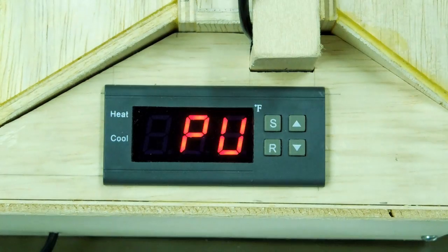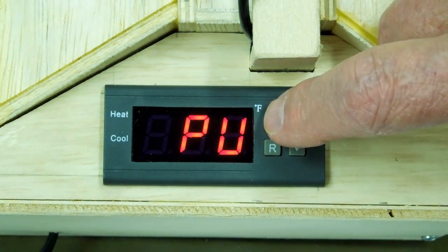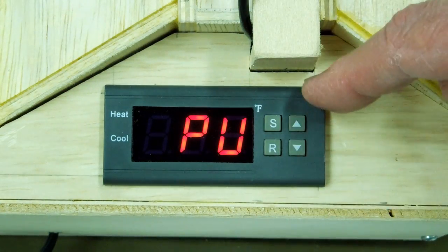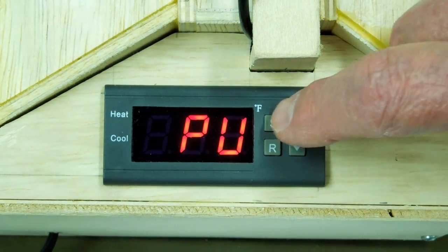Go to the next one which is PU, a delayed start. I have that set at zero. So when it gets 1 degree below the set temperature, it comes back on immediately.